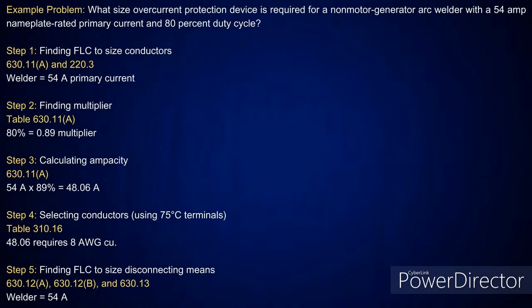Now I'm finding a percentage again. So I'm going to come over and look for a non-motor generator type. I'm going to come down and look at 89%, come across. It's going to tell me that the duty cycle is 80%. I got a little mistake there. Oh no, that is my multiplier, 89. So I take that 80% duty cycle with a 0.89 multiplier, and it's going to tell you that it's good for 48.06 amps.